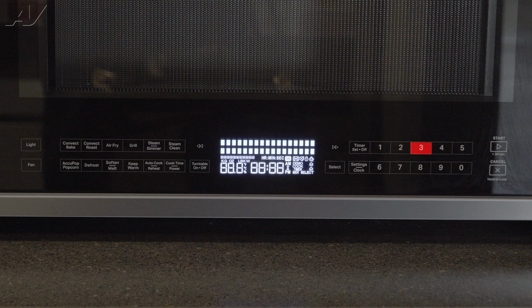Number 3 is going to be microwave relays. This is going to turn on a turbo mode on your microwave, turning on all of the relays and running at about 1200 watts. If you're running this test, make sure you have something inside your microwave - you do not want to run it with an empty cavity. When you press this, the screen will show MW Turbo. Once you're done, open and close the door and let's move on to the next step.